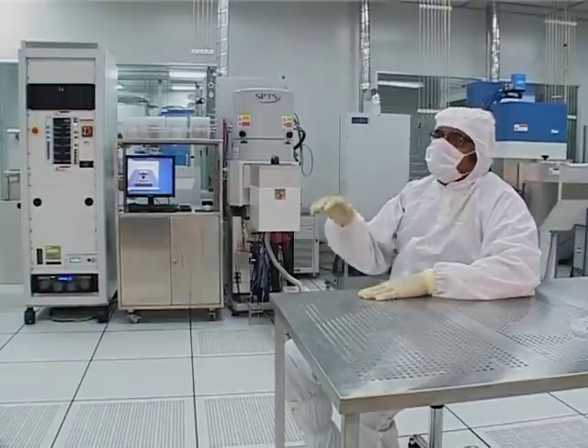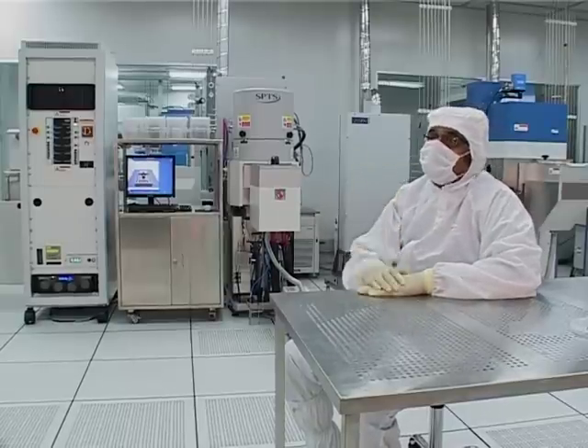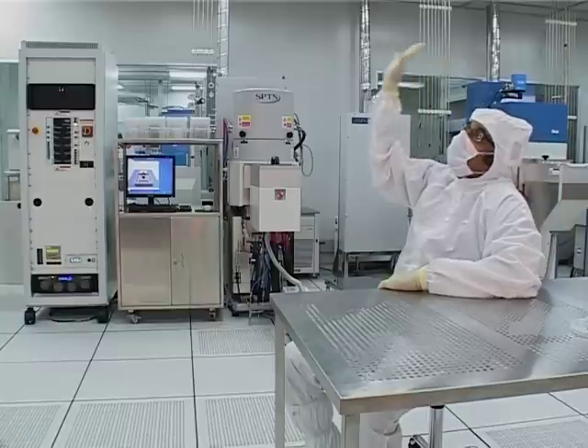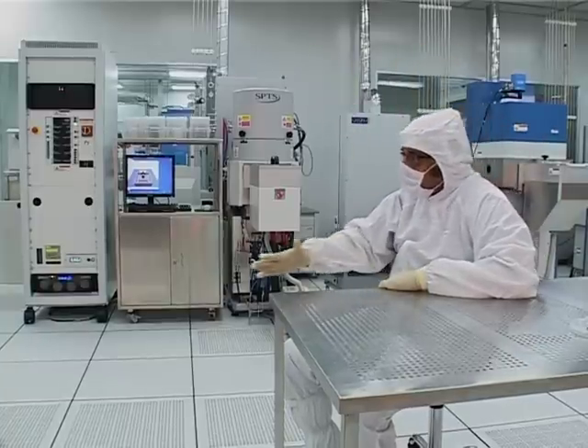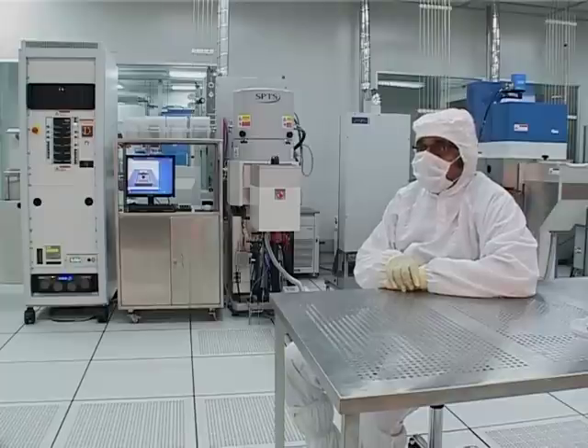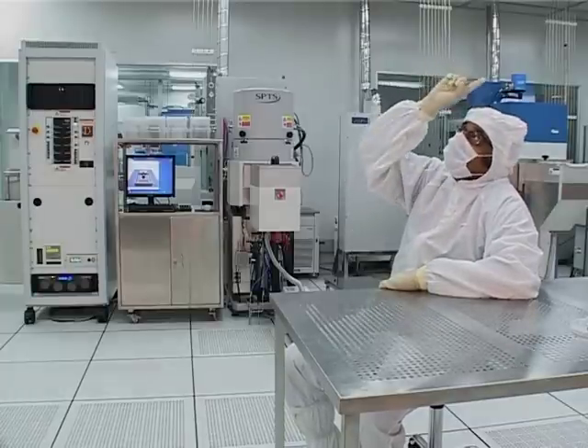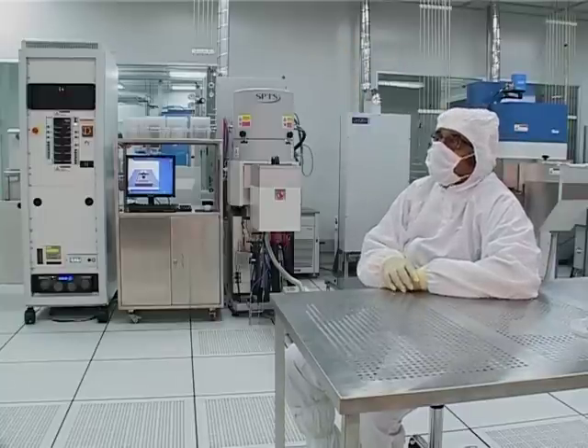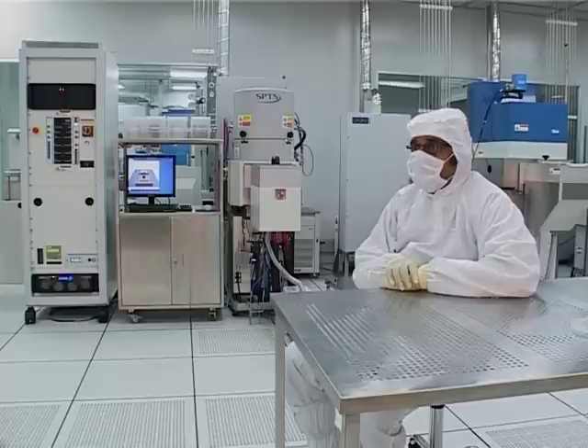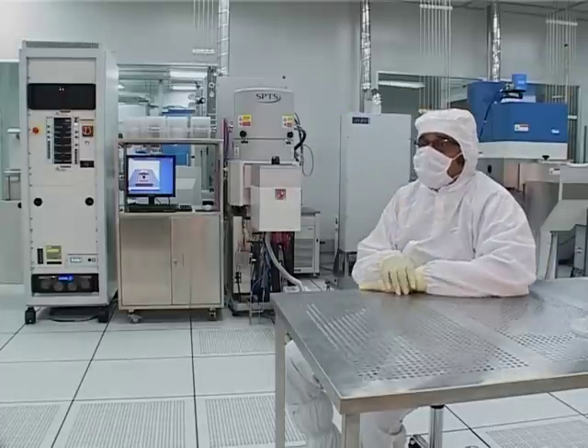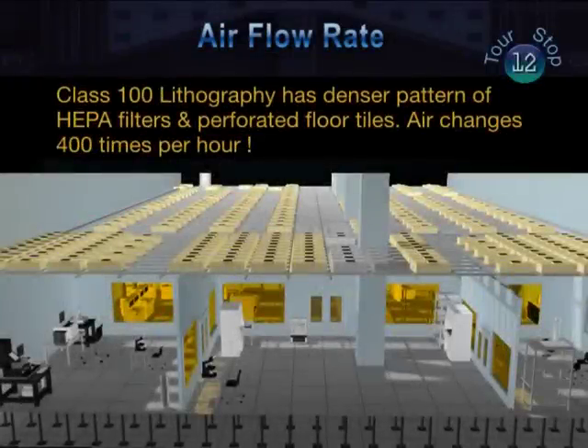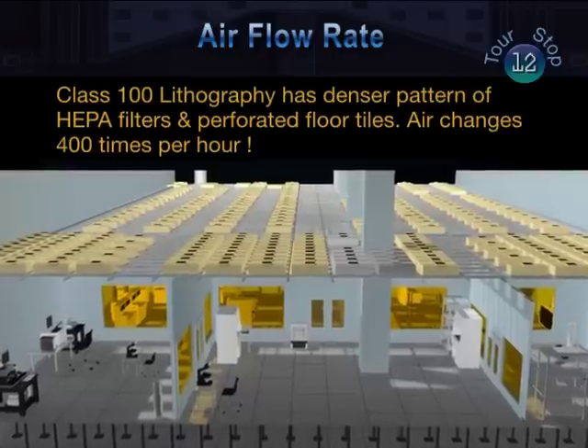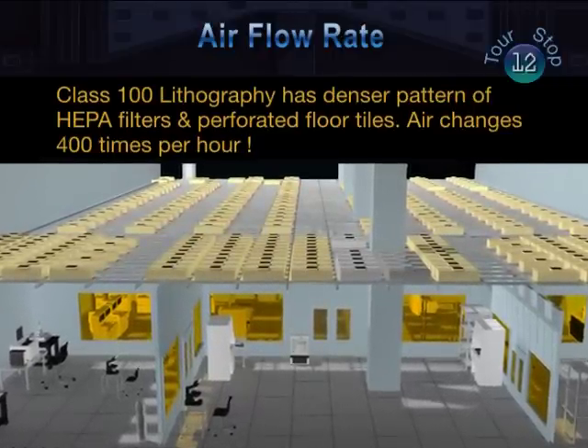Now, when you move from this class 1000 area to a class 100 area, you will start seeing dramatic changes. Here you have only partial covering of the fan filter units at the roof and also partially covered perforated tiles at the floor. When you get into the class 100 area, you will see there is 100% filter coverage at the roof and also sufficient perforated tiles at the bottom so that complete laminar flow and cleanliness is maintained. The 10 times cleaner Class 100 lithography area uses a denser pattern of HEPA filters and perforated floor tiles. The flow is kept steady at a rate that changes cleanroom air nearly 400 times every hour.